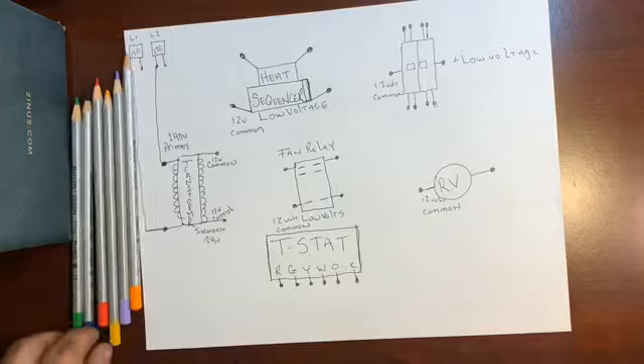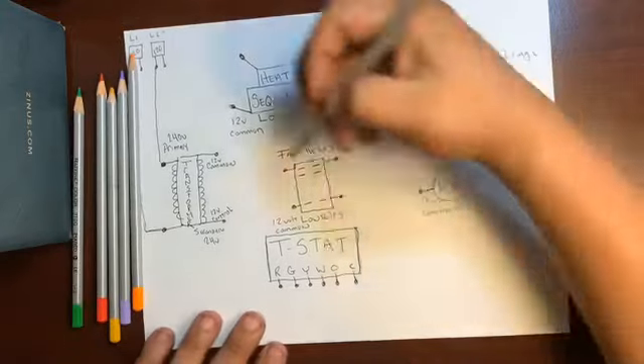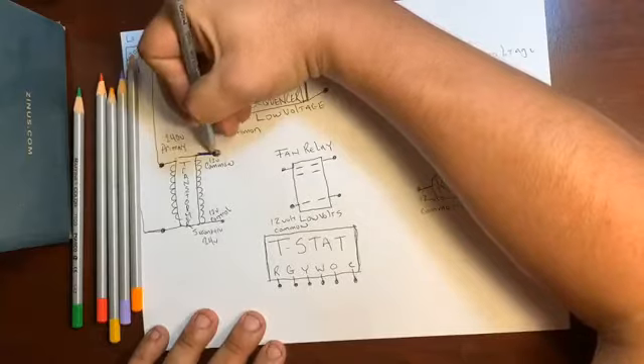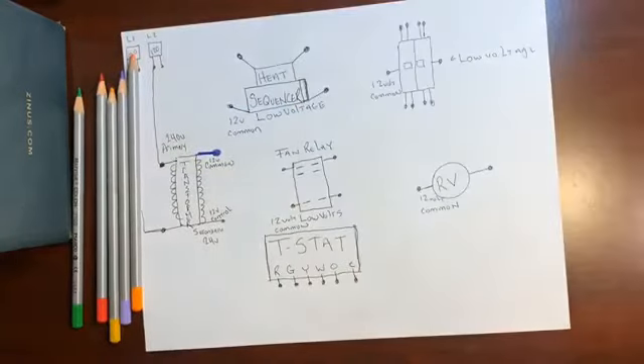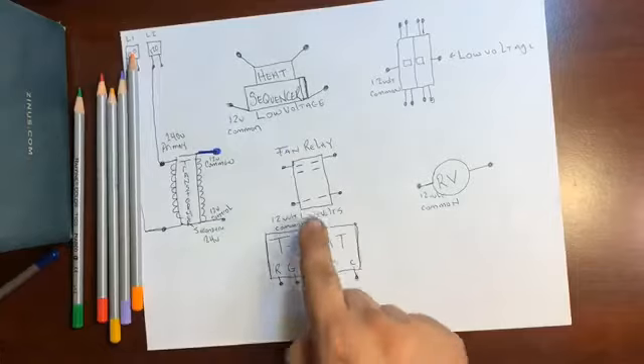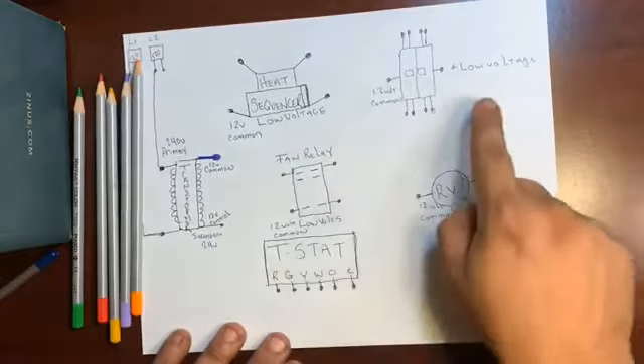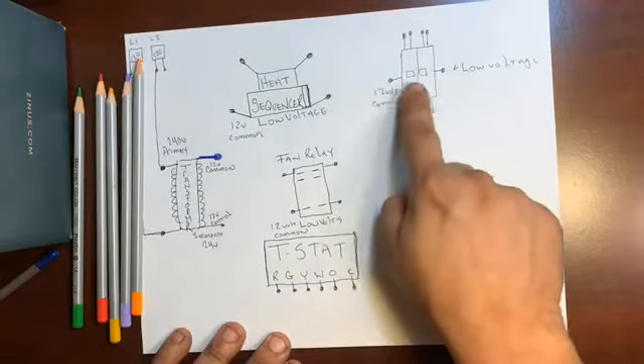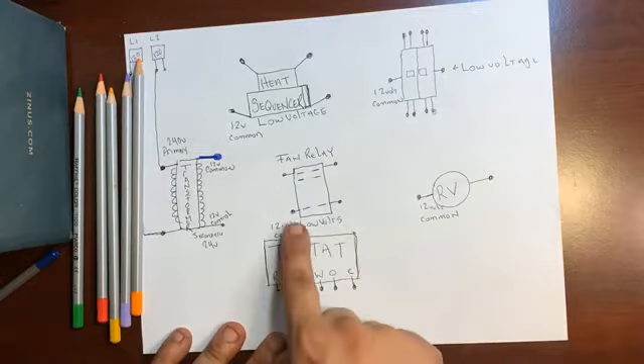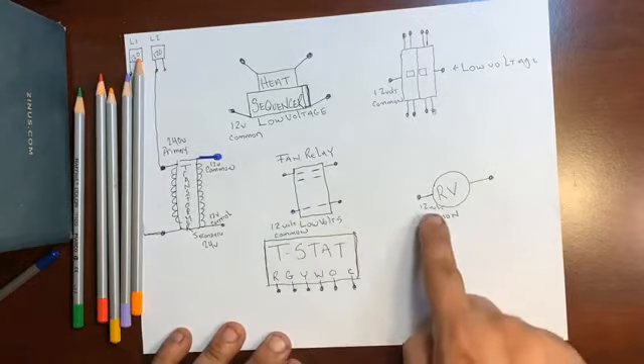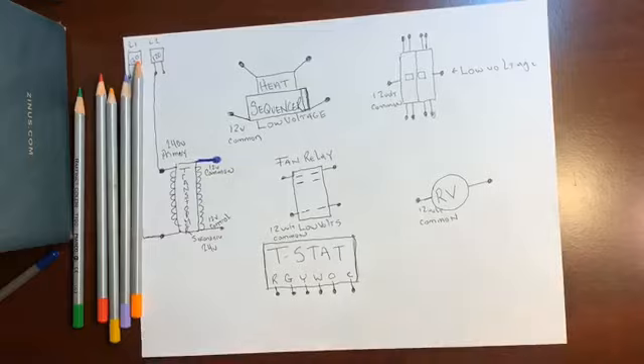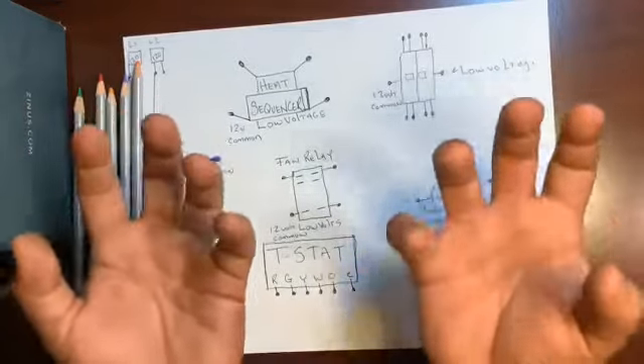Now we've been talking about 12 volt common blue, 12 volt common blue. Let's see how that all ties in. So we're gonna go with the blue line right here, coming off our 12 volt common. And let's look at our relays. Heat sequencer, low voltage has 2 legs. Compressor contactor, low voltage has 2 legs. Fan relay, low voltage has 2 legs. Reversing valve, low voltage has 2 legs. Every relay has 2 hands of low voltage.